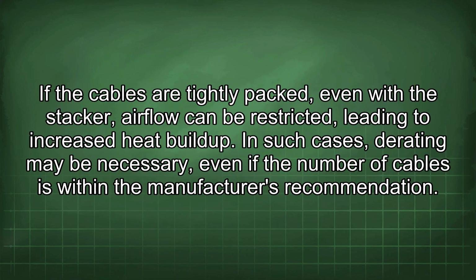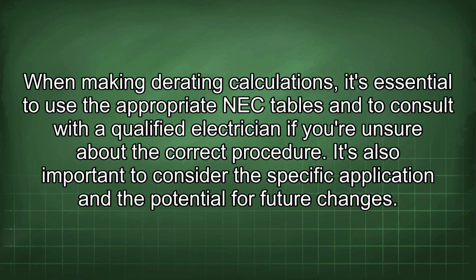If the cables are tightly packed, even with the stacker, airflow can be restricted, leading to increased heat buildup. In such cases, derating may be necessary, even if the number of cables is within the manufacturer's recommendation. When making derating calculations, it's essential to use the appropriate NEC tables and to consult with a qualified electrician if you're unsure about the correct procedure.